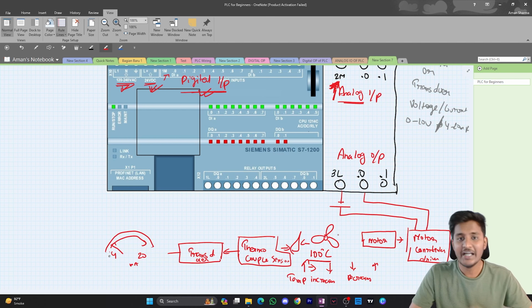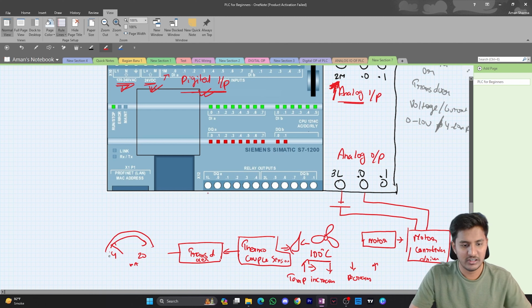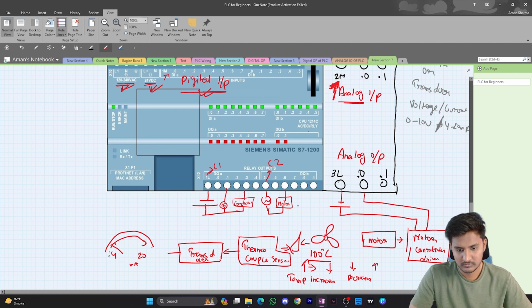Now let's move to the relay output. Relay output is basically very simple. You have 1L and 2L. You can connect one DC source here and also one AC source here because we have two commons here, common one and common two. And we'll connect our relays here or any load unit, lamp, or in any load you can connect any motor using the relays, small motors directly to the relay, or you can connect any contactor, VSIs. So this was our digital output.